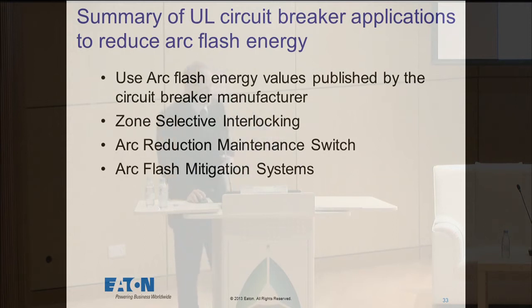Just a quick summary here is, for the UL listed circuit breakers, use the manufacturer's information. The manufacturers are a very good resource for the users. Go to the manufacturers and use their information that they've developed for their breakers to apply. Like I showed that chart, they could give you application information. Zone selective interlocking is a feature that's been around for many years, well proven in the industry, but now used for another purpose beyond just selective coordination purposes. Arc reduction maintenance switch, another new technology that some manufacturers offer. Talk to the manufacturers, and very similar for arc flash mitigation systems. So that was my very quick overview of arc flash hazards and some of the technology that circuit breakers have today to address it.